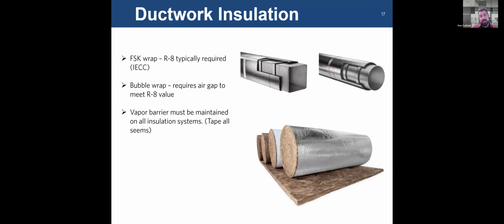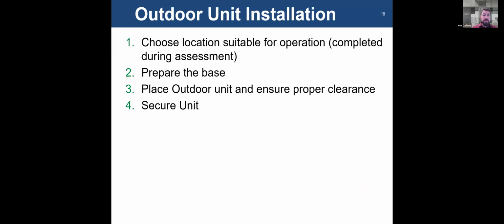And your vapor barrier must be maintained. What I mean by the vapor barrier is that all this insulation that you're wrapping on this ductwork needs to be sealed. All your joints need to be taped. When you get to a unit or a transition or whatever it might be, the insulation needs to be taped to that unit or transition to maintain that seal, right? Typically it's humid air that would go in here and potentially cause condensation in here. So hence the name vapor barrier. So again, just make sure everything is sealed and tight and taped.